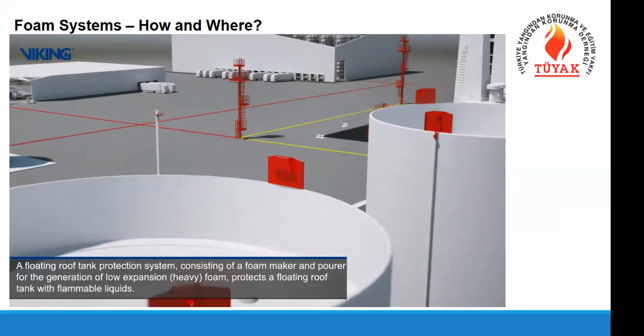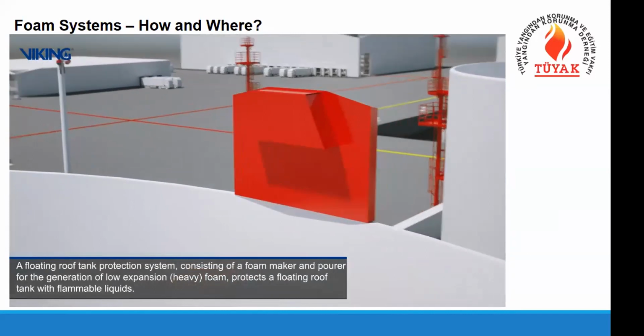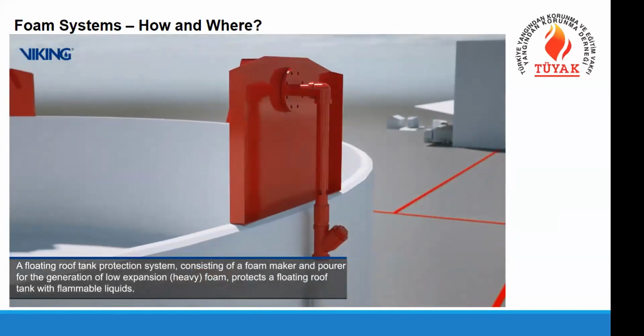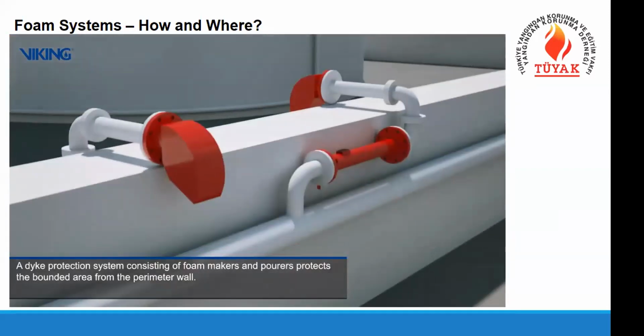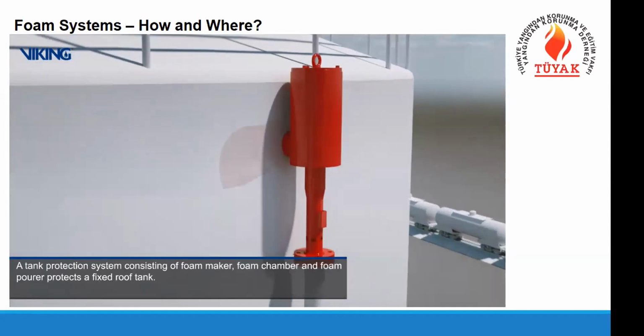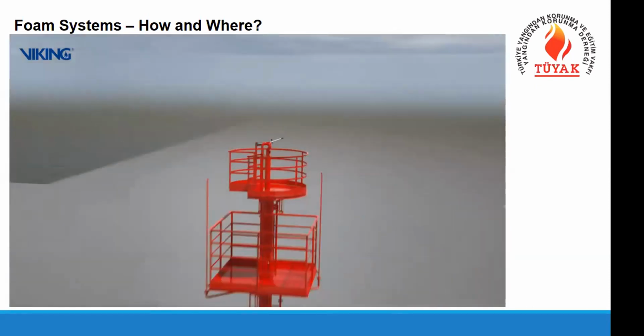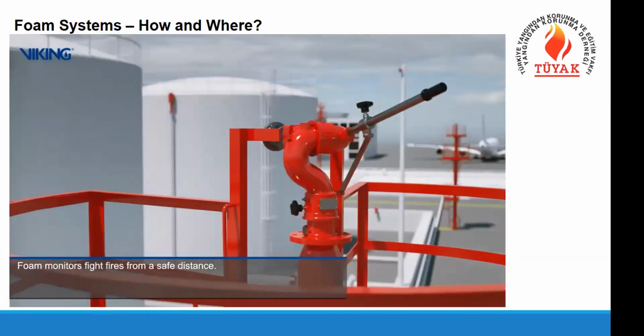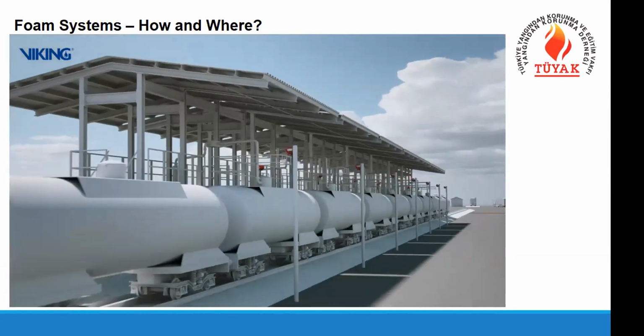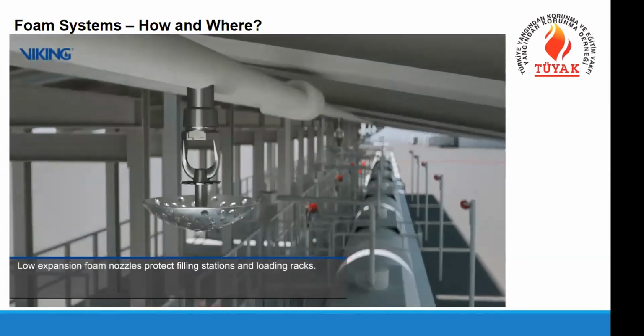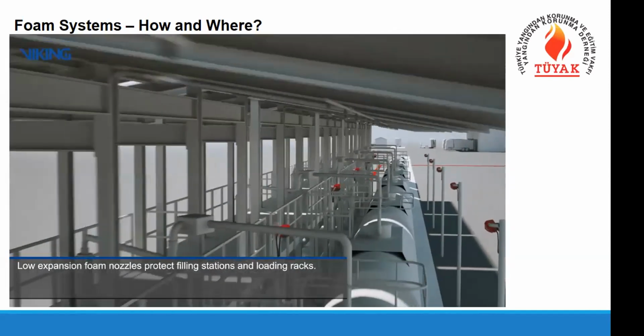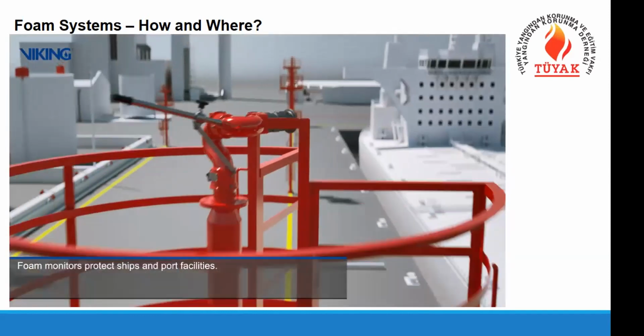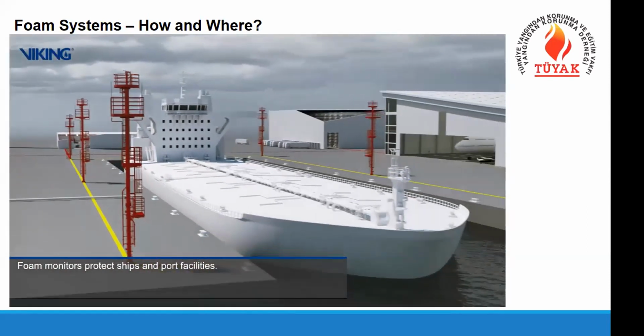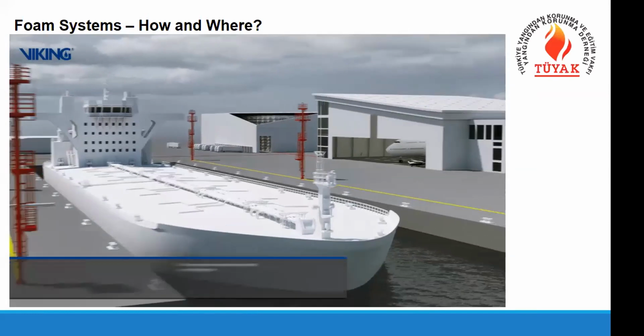in the related area. These devices are specially designed for this kind of tank protection, and have special items to expand the foam into a protection foam. There are also dikes besides the tanks, and on top of closed tanks we have different devices like foam chambers that expand the foam in the necessary amounts. For long distance throw, we have monitors, which maybe some of you have seen in the movies. In the loading racks and trailer areas, we have deluge sprinkler foam systems. And for vessel protection in the piers, we have monitor towers with foam systems.